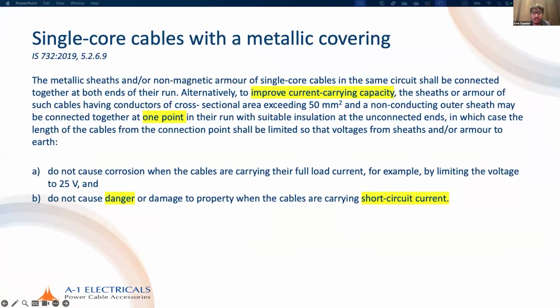Of particular concern is the single core cables with a metallic covering. When you have these cables, there's a question of whether to use a gland and connect the armoring on both sides or one side. But if you decide to do it on one side, there's a particular concern when they may move during a short circuit. So again, cleats are very important.